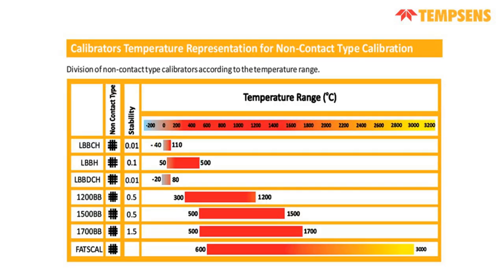Now moving ahead, for the black body calibrators. So black body calibrators come in the non-contact type calibration, and Tempsens gives non-contact type calibrators from -40 to 3000 degrees. Tempsens offers a wide temperature range in this type of calibrators, and it ranges from -40 to 3000 degrees.